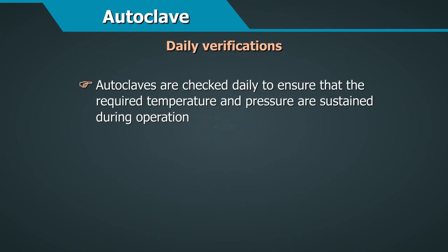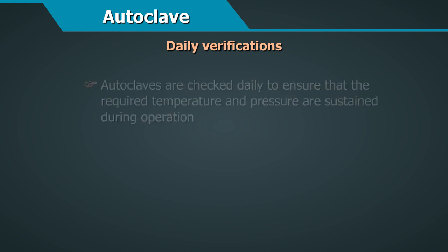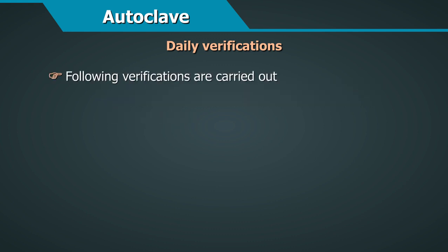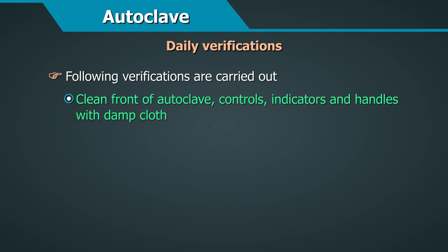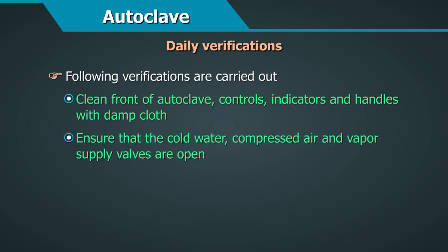Daily verifications. Autoclaves should be checked daily to ensure that required temperature and pressure are sustained during operation. Before initiating the sterilization processes, the following verifications will have to be carried out. Clean the front of the autoclave, controls, indicators, and handles with a damp cloth. Ensure that the cold water, compressed air, and vapor supply valves are open.